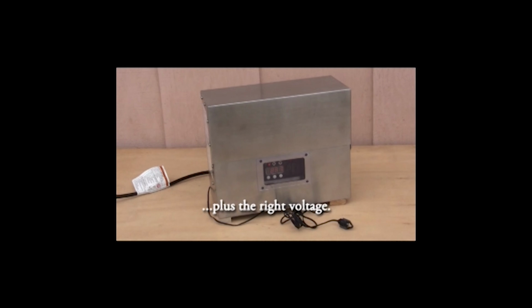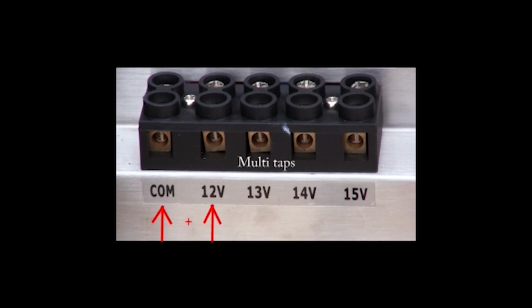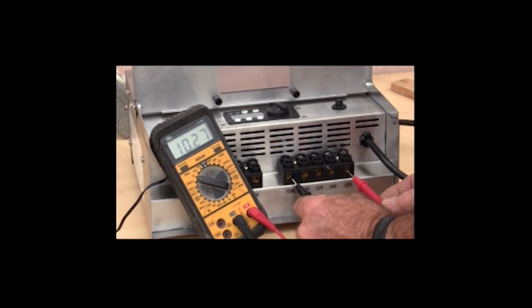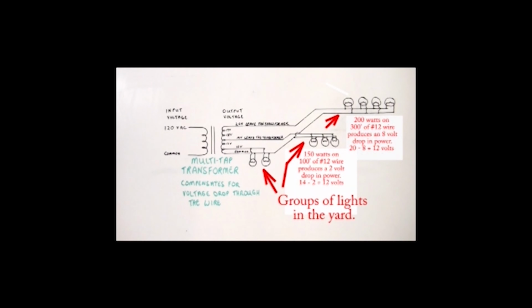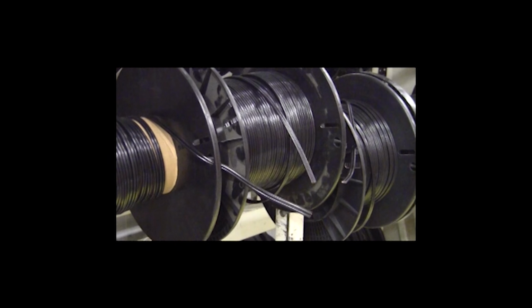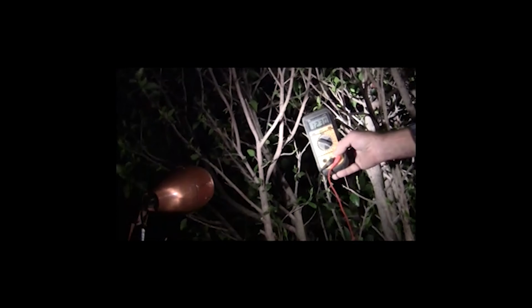Some transformers have a nice feature called multi-taps. Connect the wire to one set of taps or terminals and you send out just 12 volts. But connect it to another set of taps on the transformer and you send out maybe 15, 18, or even 22 volts. If some of the lamps are a couple hundred feet away, split up the strings of lights and connect the furthest lights to the higher voltage tap. The wire itself drains off some of the voltage, but the lamps way out there will still get 12 volts. If the system was designed well, all the fixtures will get pretty close to the same voltage and they will all appear equally bright.